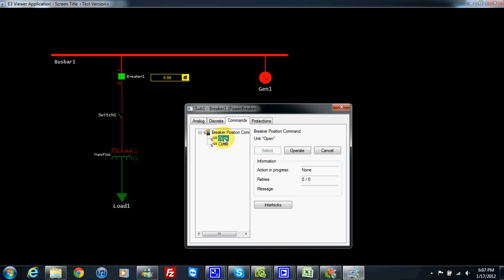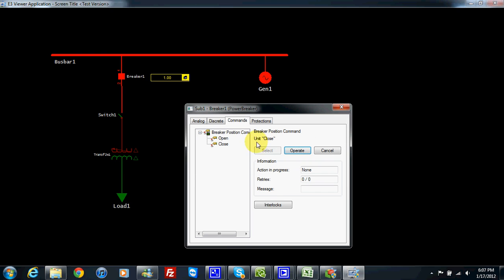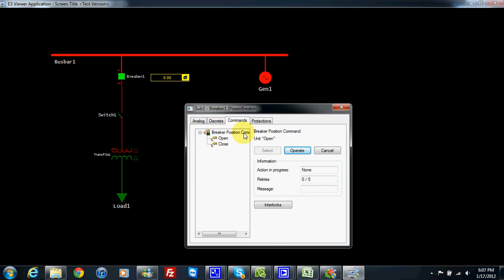I can also choose to go to measurement, where I have a type command panel. I can do the same thing here. We did not choose the select before operate mode, so the select button is not enabled. I can choose to close, then operate — yes. And open, operate — yes. We can see the breaker is changing and the symbol is changing color. We can see the current is going through when the breaker is closed, and when we open it the current will stop.